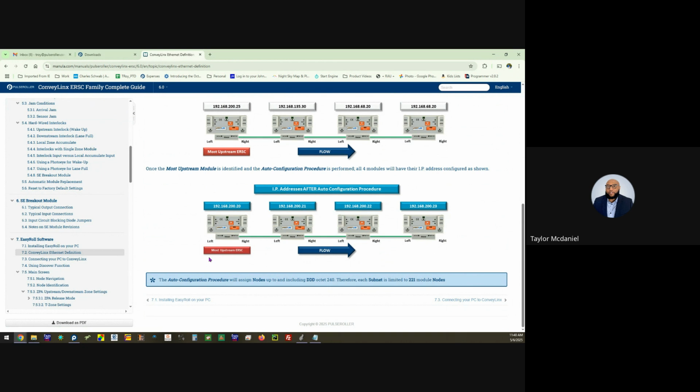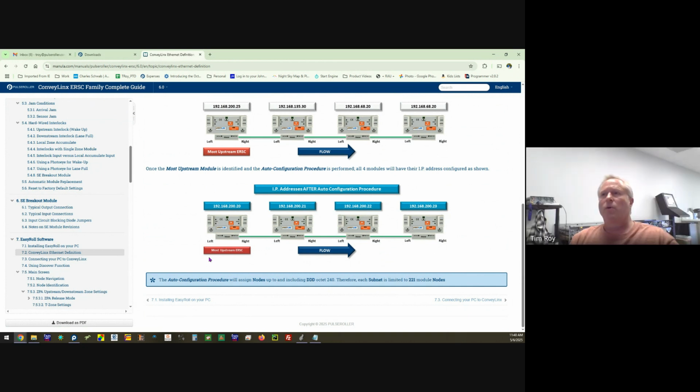So we had 128 cards, and you're saying that... let's see what the good multiplier is for 128. I mean, you don't actually have to stagger the RPI rates, but that is something that can be done if you're noticing disconnects.